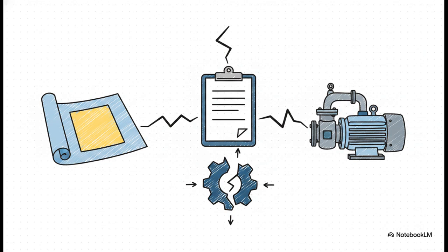The drafting team meticulously updates the HAC drawing to revision C to reflect a new wider Zone 2 area caused by higher process pressures. But wait, the electrical engineering team doesn't update the Ex-Equipment Register. It's still sitting at revision 8. Suddenly, you've got a massive conflict. The drawing dictates one thing, the equipment register dictates another, and the actual physical plant is out there doing a third thing entirely. The documents are no longer providing a unified defense, they're telling three slightly different lies.